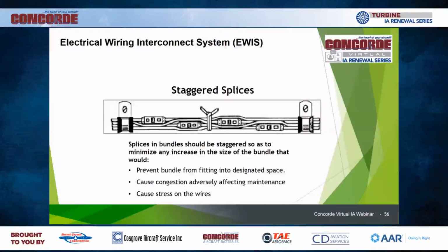Staggered splices—does everyone know how to install splices so they don't end up 10 inches round on the bundle? Splices in bundles should be staggered to minimize any increase in bundle size that would prevent it from fitting into its designated space, cause congestion that adversely affects maintenance, and cause stress on the wires themselves.